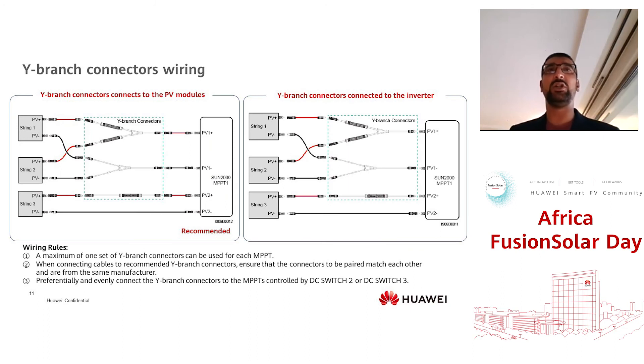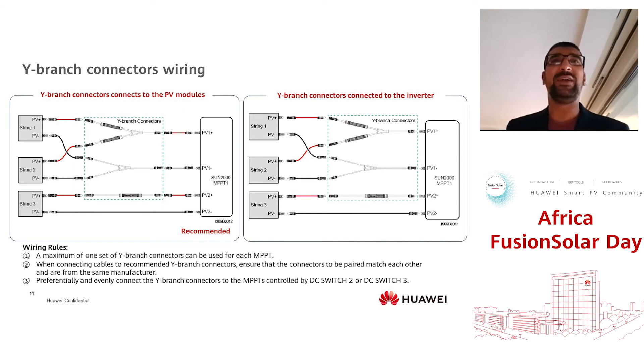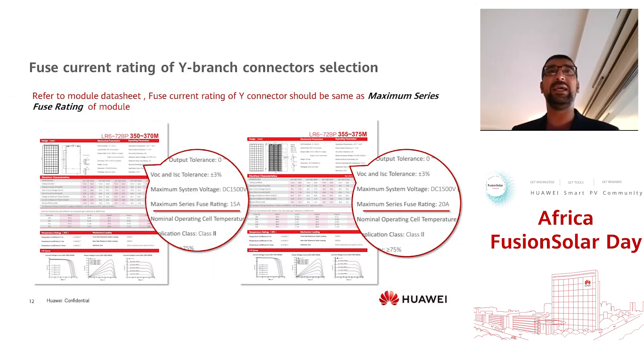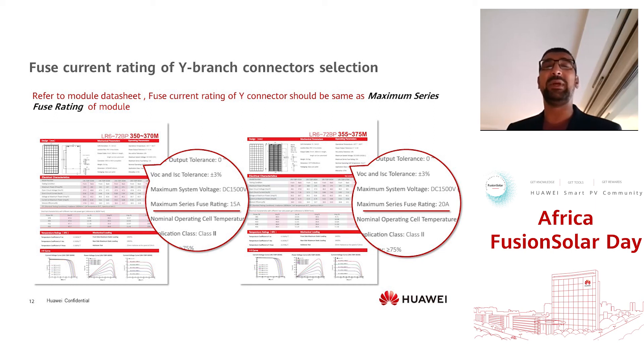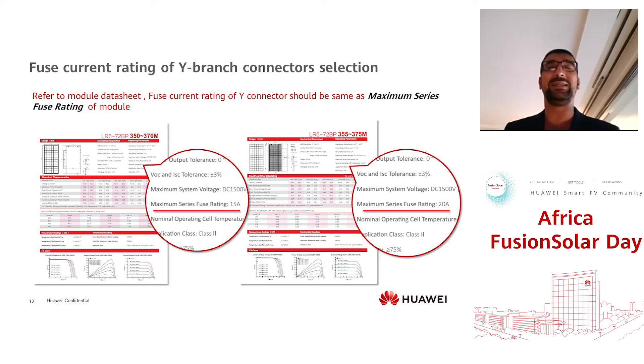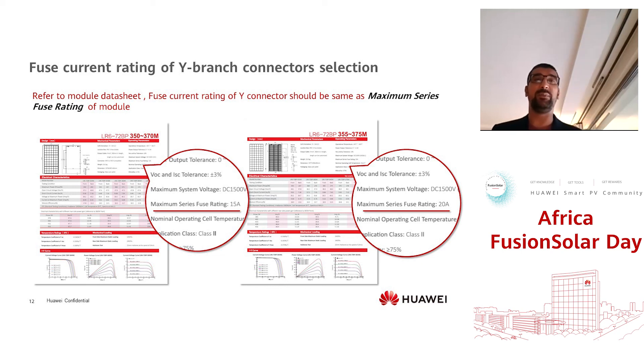The configuration shown on screen shows the recommendation for how Y branch connectors should be connected correctly, with the inline fuse on the positive point of the inverter connection. To calculate the fuse rating for the Y connector, you extract the maximum series fuse rating from the PV module datasheet and select the correct fuse to ensure the inline fuse is rated to the PV module's specification while also keeping within the parameters of the PV inverter.